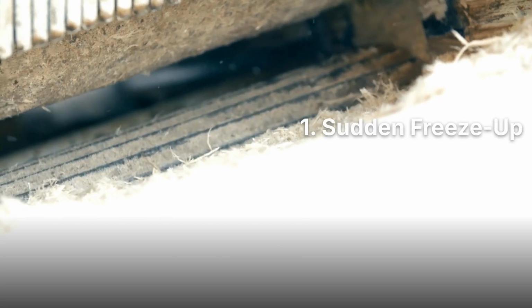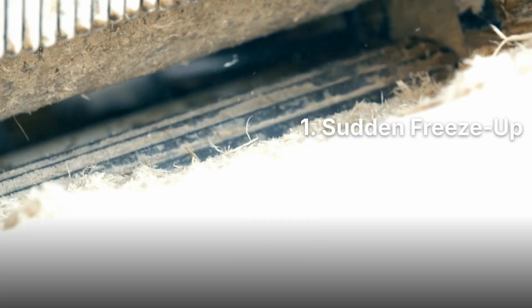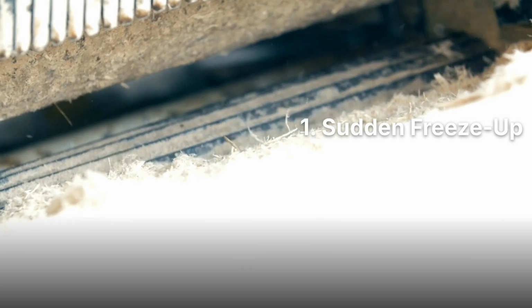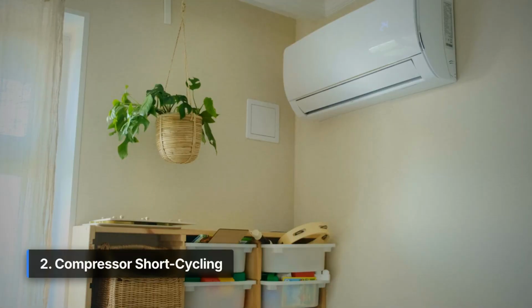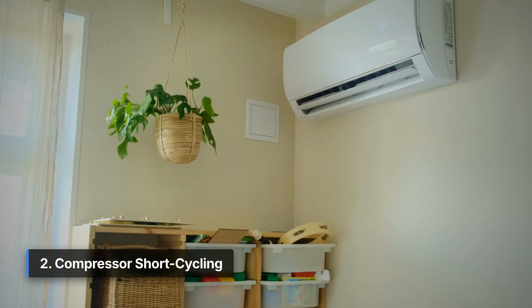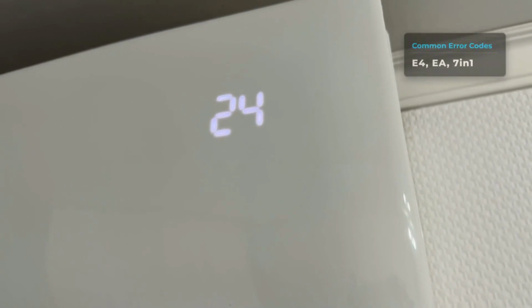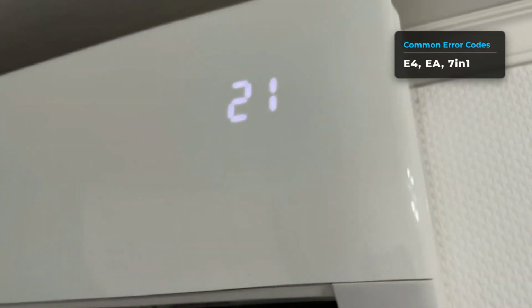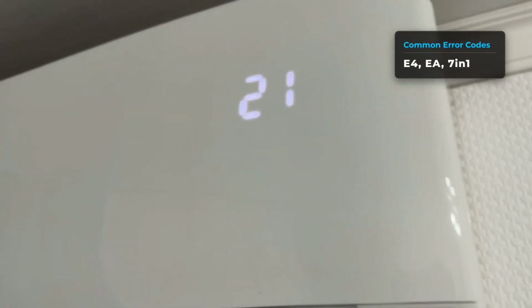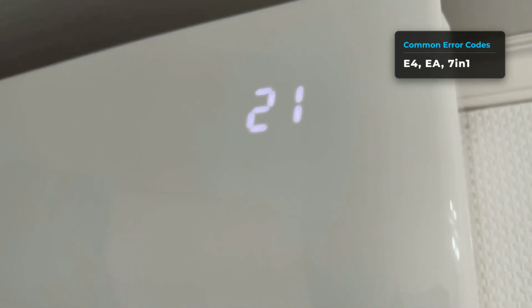The room turns into an icebox, or worse, the evaporator coil starts icing over because the sensor incorrectly tells the board the room is still 30 degrees Celsius. The compressor kicks on for 2 minutes, then abruptly turns off without cooling the room at all. The PCB falsely thinks target temperature has been reached. Hisense units frequently trigger specific fault codes when sensor resistance goes out of bounds, commonly E4, EA, or 7 in one error indications. If you're noticing any of these, don't guess, test.